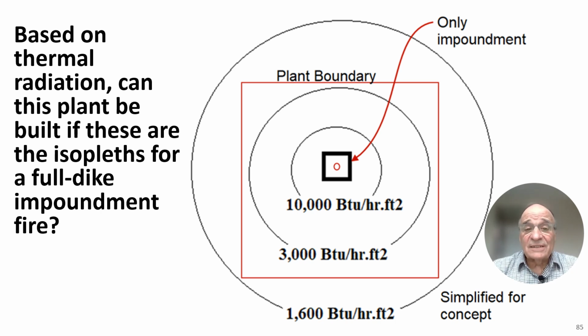Now this slide shows this same exact isopleths as the earlier slide. However, this is not for a design spill. This is for a full dike impoundment fire. And what does the code say about a full dike impoundment fire? It says that the 3,000 and the 10,000 BTU limits are within the property line, so that's acceptable.